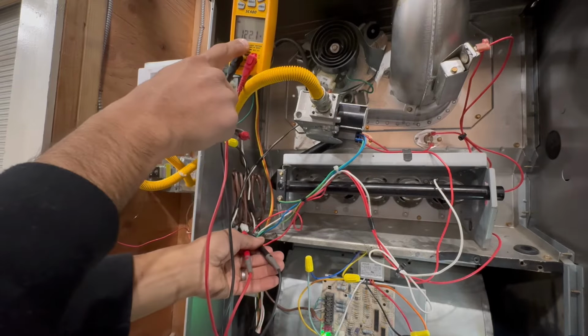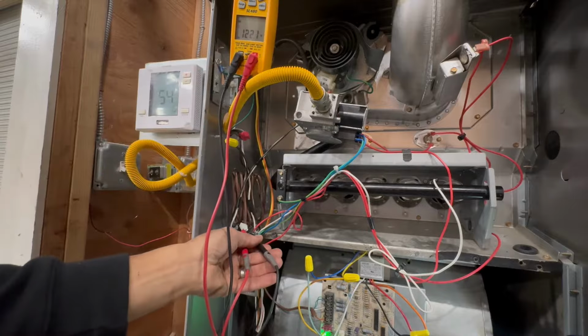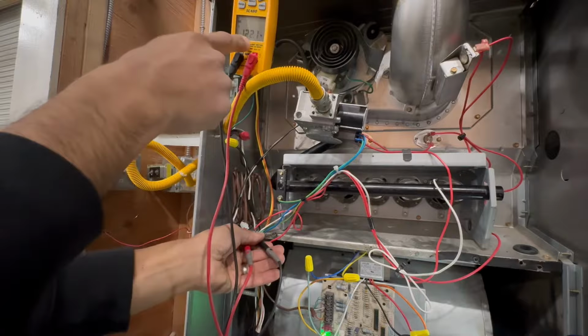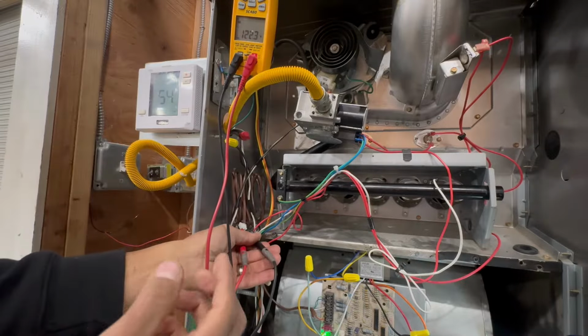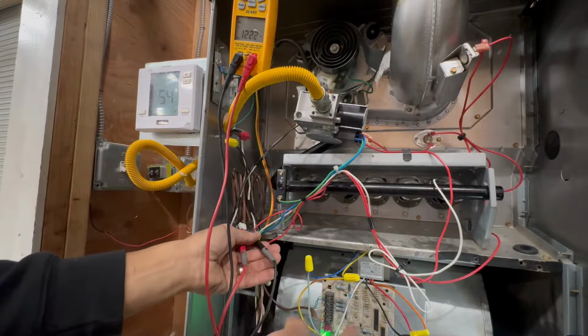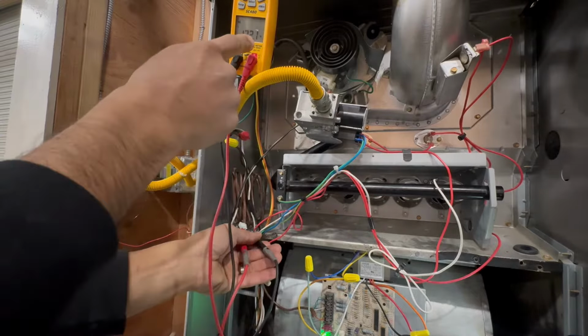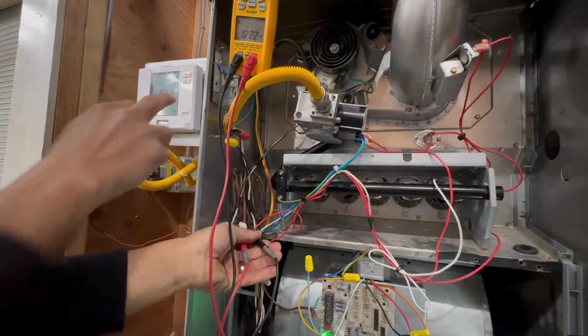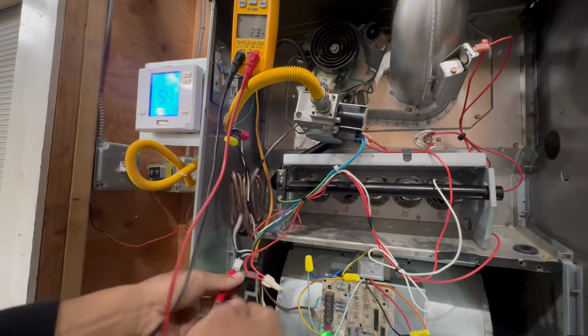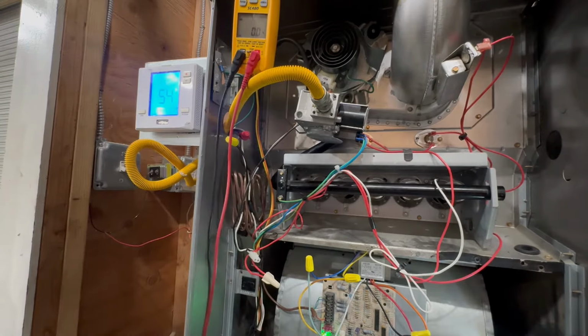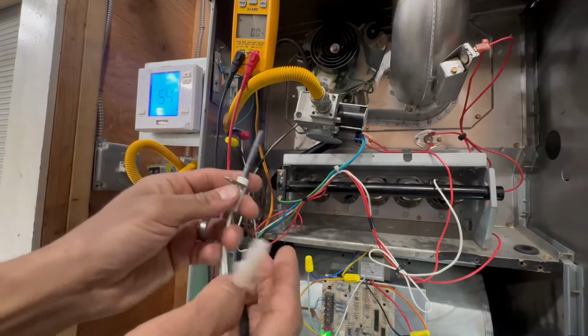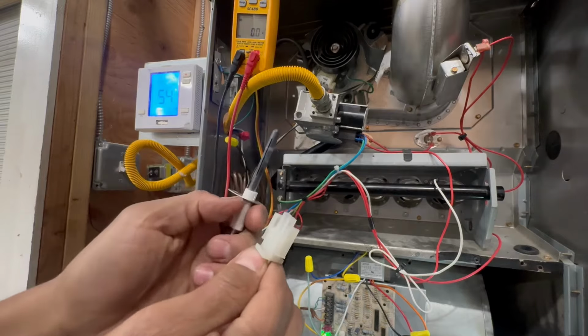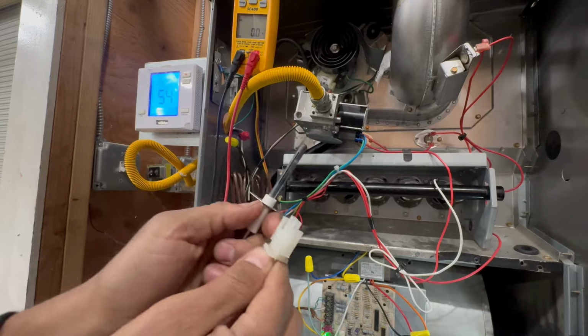You see, I'm getting 120 volts. I heard that little relay kind of click, but yeah, it sends 120 volts out. So these are the two tests that you do. Make sure that the board is sending 120 volts, and then with no power present, you would check the hot surface igniter and check that you're getting a resistance value. You do not want to get an open line on these.